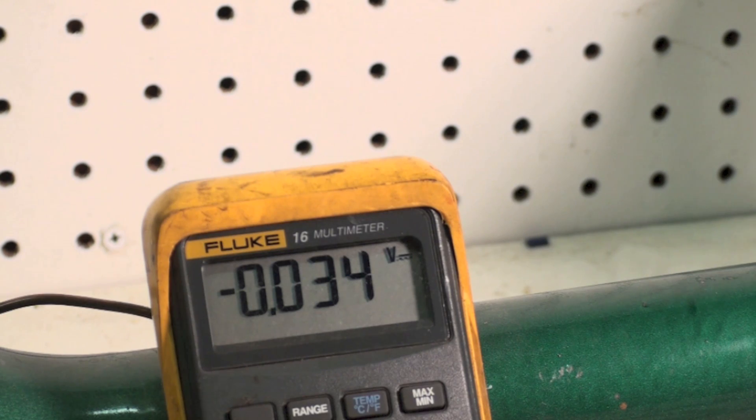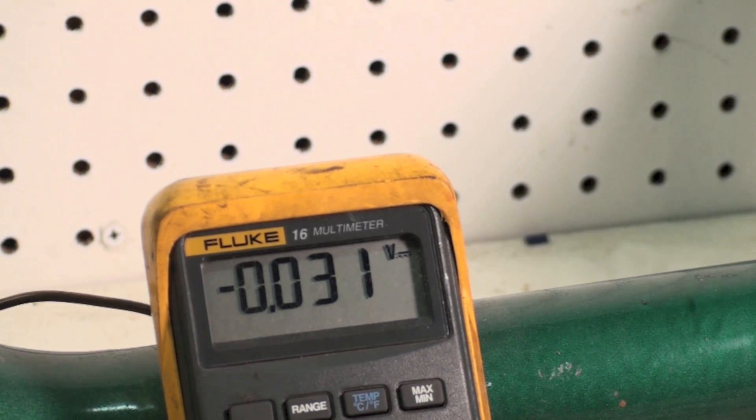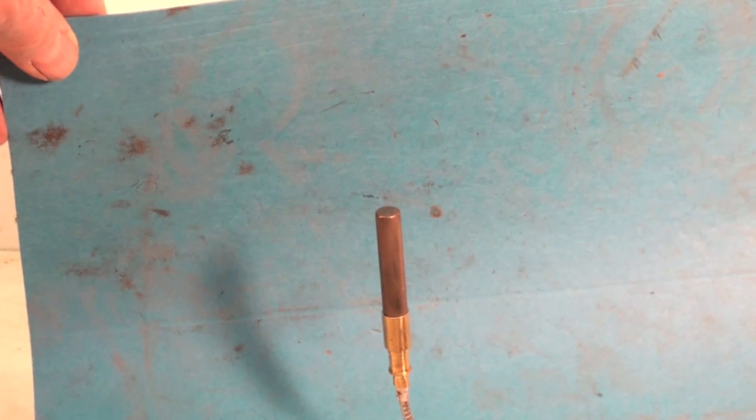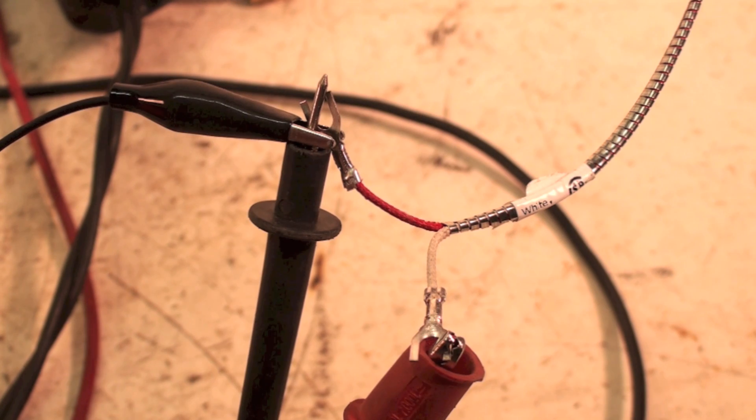That's the thermopile. It's not different, it's just got more stuff. It's bigger around than the thermocouple, and essentially what it is is a whole bunch of thermocouples all wired together inside. That's what the thermopile looks like - it's about three-eighths of an inch across.